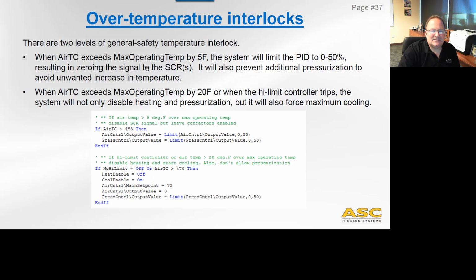So we start with temperature interlocks. Now, the standard should be that there are two temperature interlocks, okay? One is looking at the air temperature being greater than 5 degrees over maximum, and in this case 450 would be maximum, so 455. And then we want to look at the high limit controller, okay? So the high limit controller trips; there's one where AirTC is greater than 5 degrees, and there's another where AirTC is greater than 20 degrees above maximum.